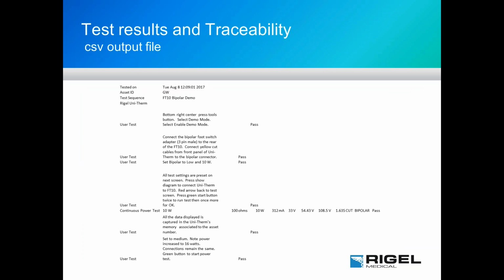One thing that I mentioned is that when we're running an auto test sequence in our ESU analyzer, this thing called the Uni-Therm, we capture test data, all associated to the asset number. So this is just a little snapshot of the type of information we capture. It shows you the test date, the time, the asset ID, what the test sequence was that we utilized for this test, and some user comments that assist with the setup and what we're trying to do in the test. Then if you go about two-thirds of the way down, just lower than halfway, you'll see the actual outputs of a test, where we capture the resistance value, everything we saw on the screen: the output wattage, true RMS power, true RMS current, RMS voltage, peak to peak voltage, in this particular case what the crest factor was, and it was indeed a bipolar test.